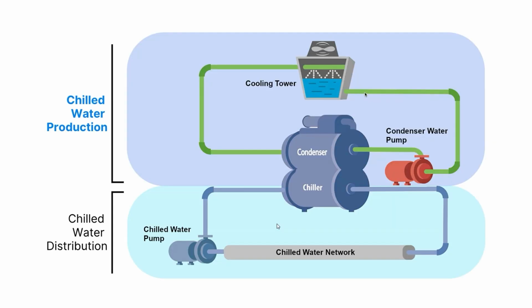Huge opportunity for optimization. We see massive potential there in every water-cooled system. We should differentiate between air-cooled and water-cooled. But where we do have cooling towers, we see on some of those smaller plants quite often, if the design conditions say condenser water leaving temperature or the chiller wants condenser water entering temperature at 29.5 degrees because this was the design condition, that will be the set point.